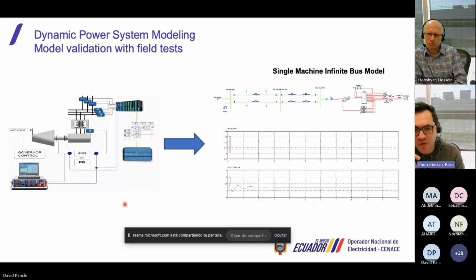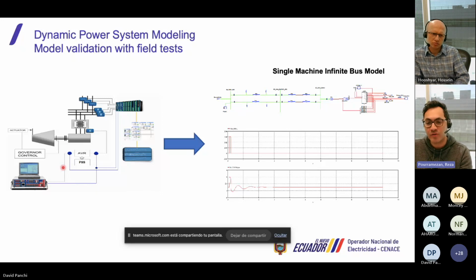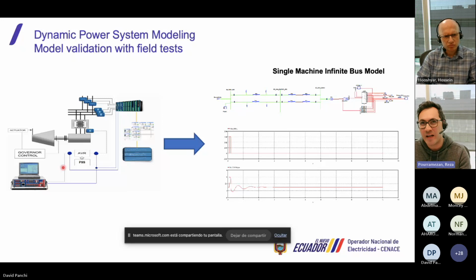Very interesting. I just have one more follow-up question. I understand that you use the Omicron and step changes and frequency variation changes to induce dynamics in the system, so your algorithm can pick up the behavior of the control systems. Have you also thought about using natural system dynamics, when an event happens, or when a fault happens, or a set point change happens naturally within the network, capturing those live data and using them for model validation? Is there any merit to that?